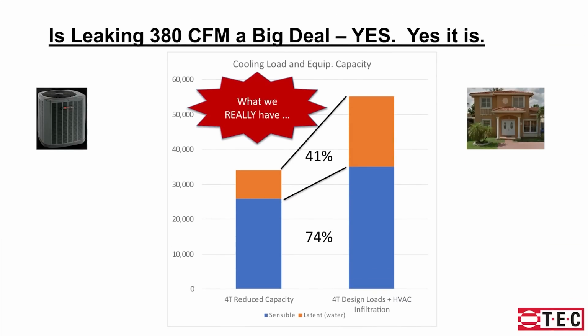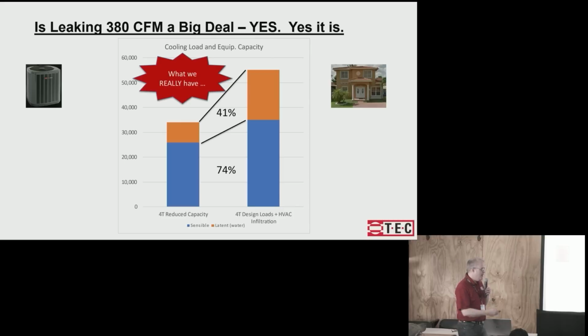Okay, here's what we really have. We are really only covering 41% of the latent load and 74% of the sensible load. So now we look at this chart, we've adjusted the calculations for the conditions we really have. Does putting a 3-ton system on a 5-ton load look more like what's going to happen, that you're going to slip by 8 degrees on a warm afternoon? This now explains what we're seeing. That's what we really have.